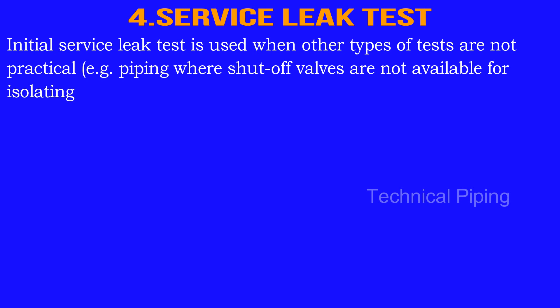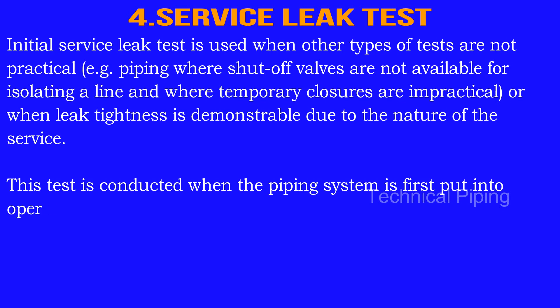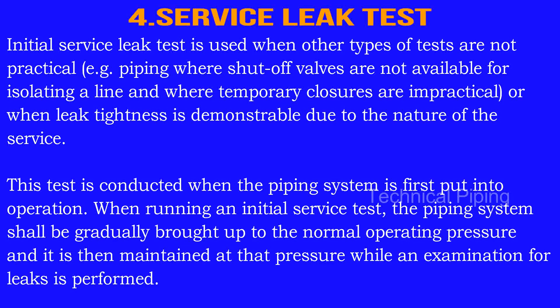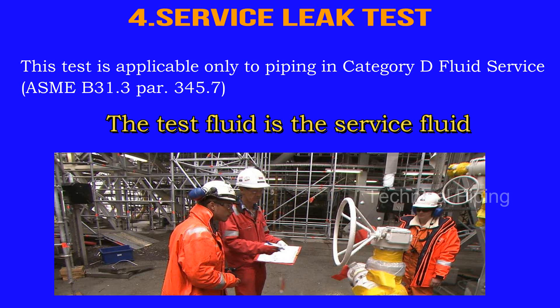Number 4: Service Leak Test. Initial service leak test is used when other types of tests are not practical — for example, piping where shut-off valves are not available for isolating a line, and where temporary closures are impractical, or when leak tightness is demonstrable due to the nature of the service. This test is conducted when the piping system is first put into operation. When running an initial service test, the piping system shall be gradually brought up to the normal operating pressure, and it is then maintained at that pressure while an examination for leaks is performed. This test is applicable only to piping in category D fluid service. For more reference: ASME B31.3 para 345.7.